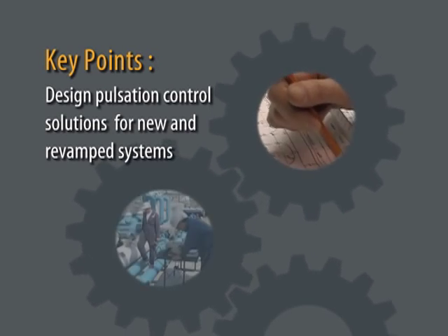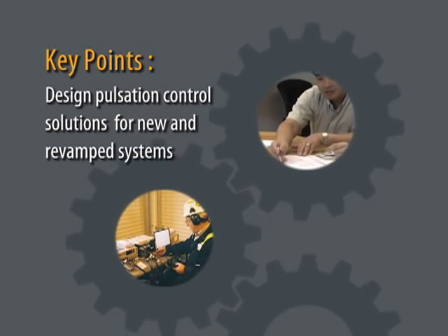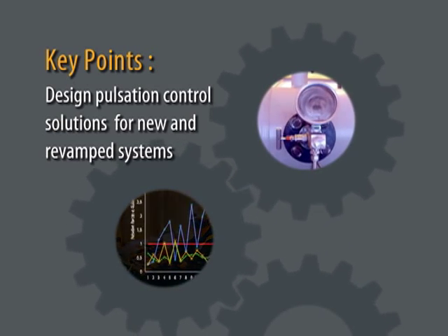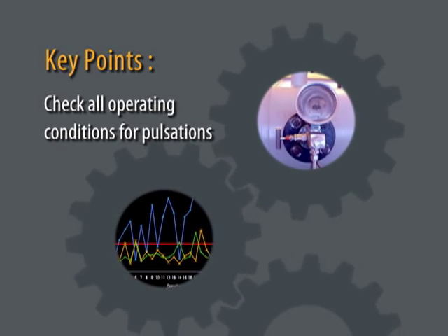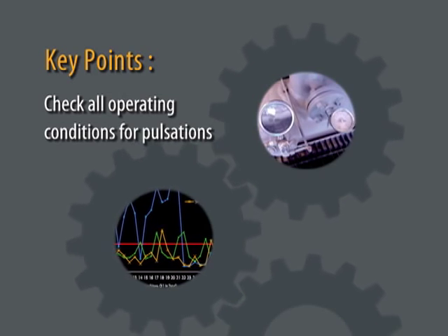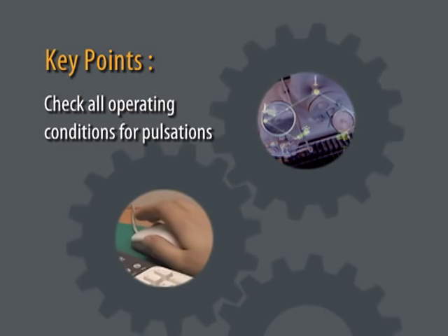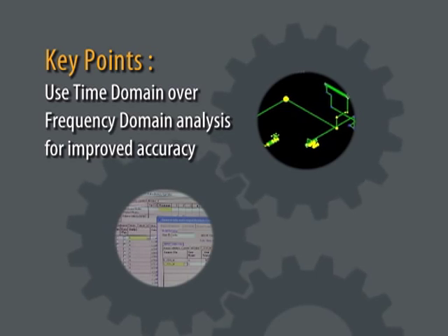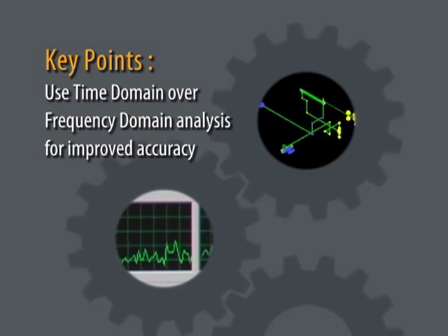Beta's role is to design a pulsation control solution that reduces pulsations to acceptable levels on new systems or revamps. When doing a pulsation study, it is important to check all operating conditions for pulsations, including the adequate speed range for fixed and variable speed applications. Time domain modeling techniques should be used for improved accuracy over the older frequency domain approaches.